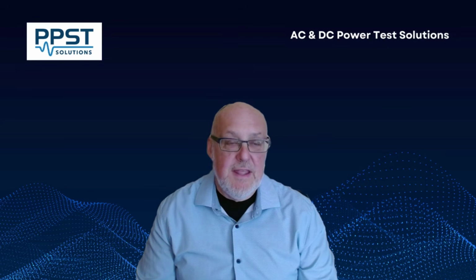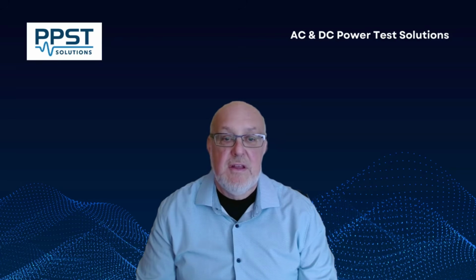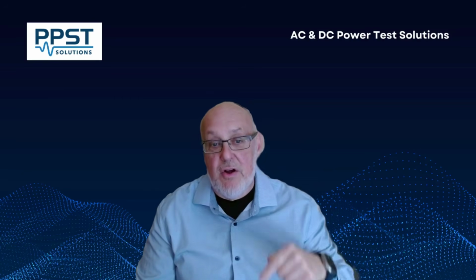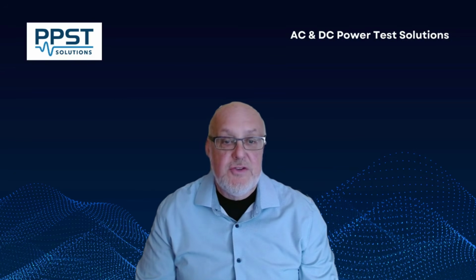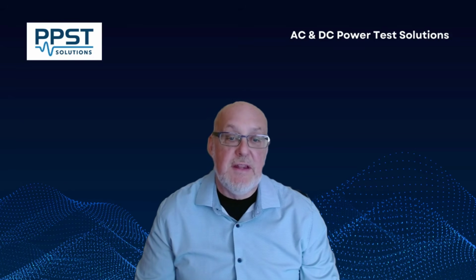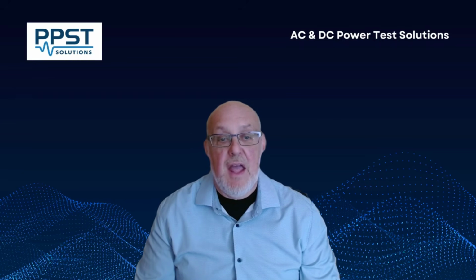Great question. In test, it's key to test ideally your four corners, as they call it, meaning high voltage, high current, low voltage, low current, and ensure that your product is going to perform correctly. How that changes and the rate that it changes is something that is an anomaly that takes place with the utility company. And so to have repeatability in tests, to understand how your product performs under those conditions, needs to be done in a very precise and accurate manner.